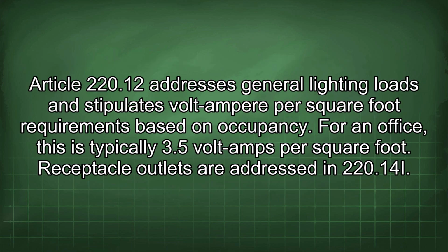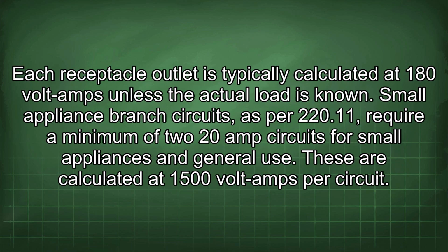Article 220.12 addresses general lighting loads and stipulates volt-ampere per square foot requirements based on occupancy. For an office, this is typically 3.5 volt-amps per square foot. Receptacle outlets are addressed in 220.14(I). Each receptacle outlet is typically calculated at 180 volt-amps unless the actual load is known.